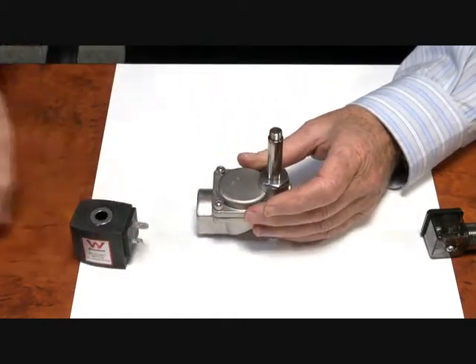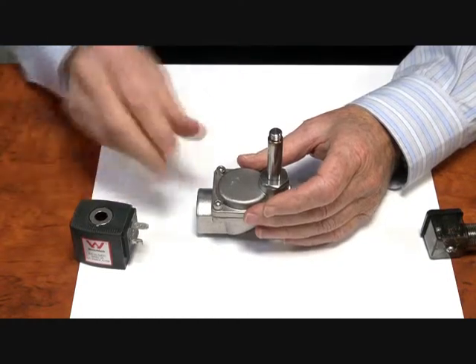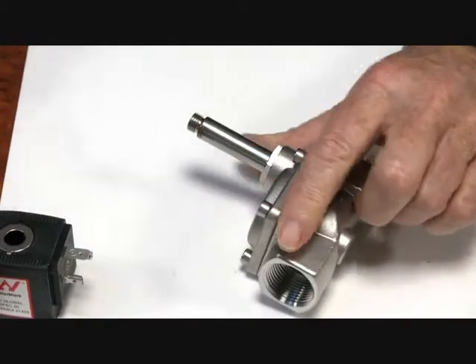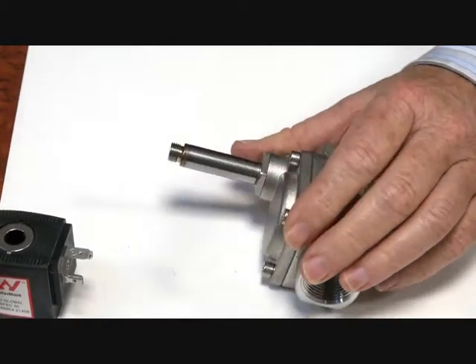This is a differential valve. It requires 0.3 of a bar or up to 1 inch, or 0.7 for the larger sizes up to 2 inch.